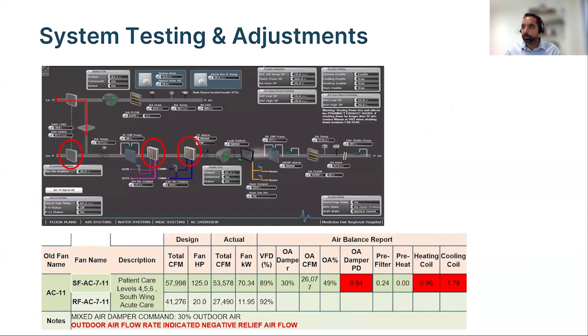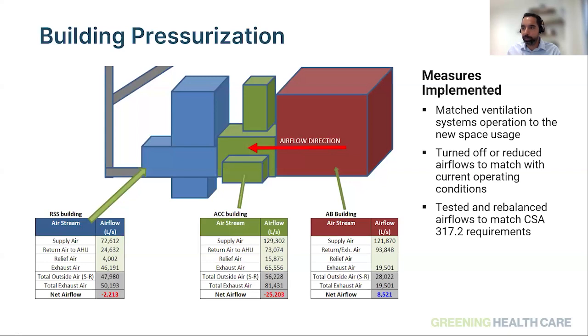So given the time, I'll run through a couple more and get Jared's input. This was one of the measures uncovered as part of the air testing: because the return fan wasn't operating as intended, it was trying to draw air from the exhaust side, which would have otherwise gone undocumented had the air testing not confirmed it, and it was resulting in a higher outside air percentage on the system. So again, air testing was key to uncovering this.